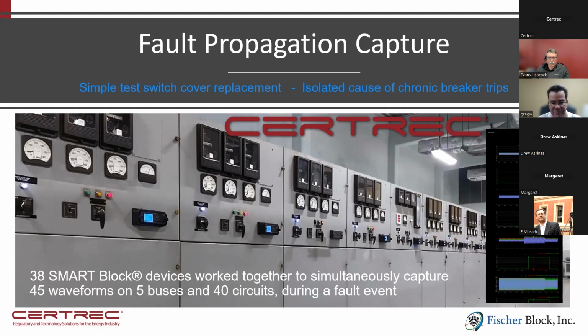That third panel from the left does not have one of our devices, but you can see that plastic cover that covers the test switch. The test switch is there in order to run periodic testing on the relay, whether it's a microprocessor relay or electromechanical relay in this case. Those relays are doing 24/7 monitoring of the electrical signals on the grid, and when things get to a point where there's an unsafe condition out on the grid, maybe a down power line, the relay will trip the breaker.